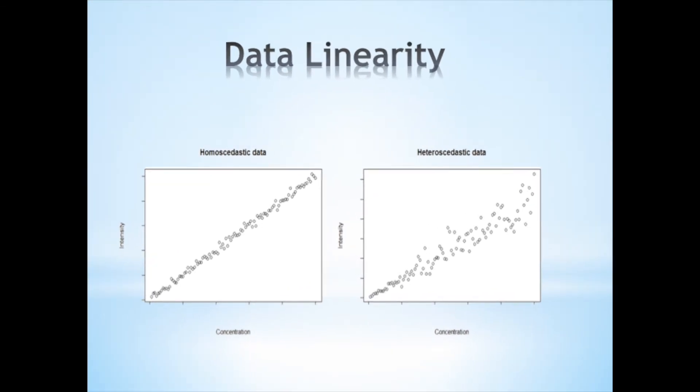A type of approach to determining the operational limits of the technique is through a calibration curve. These data should be linear and homoscedastic. Homoscedasticity describes a situation in which the error term, that is the noise, is the same across all values of the independent variables. Heteroscedasticity is present when the size of the error term differs across values of an independent variable. Increasing heteroscedasticity affects linearity of the calibration curve.